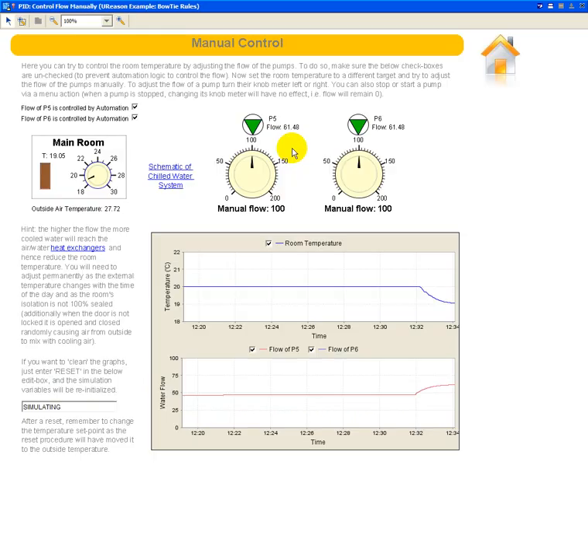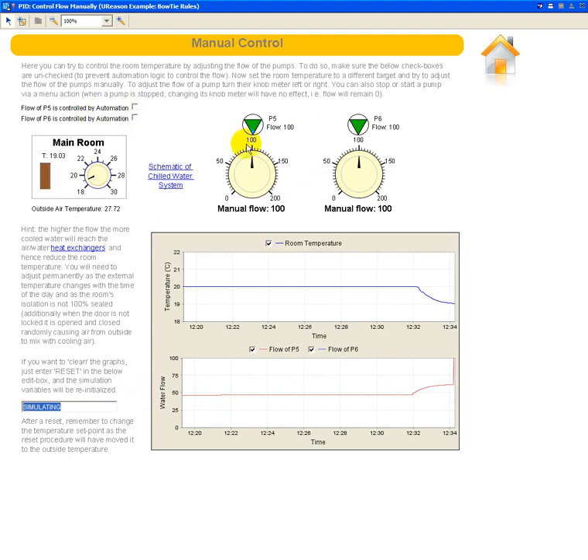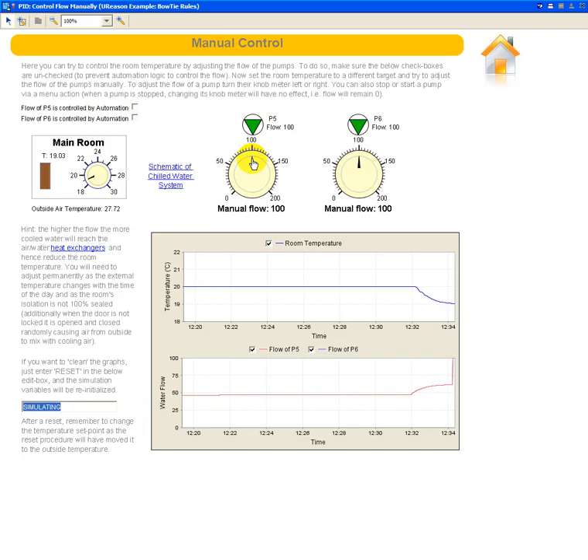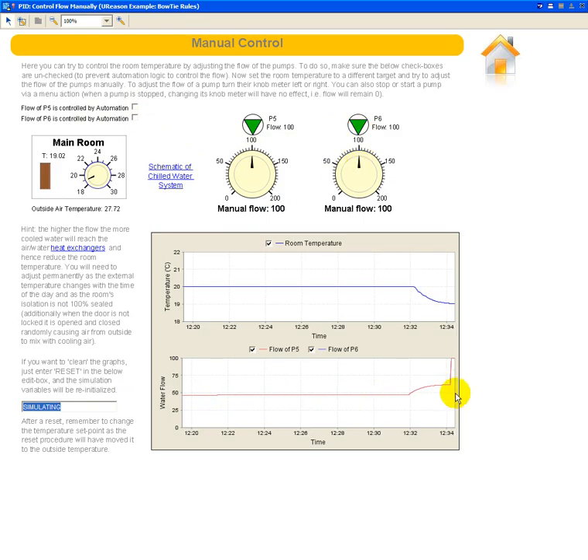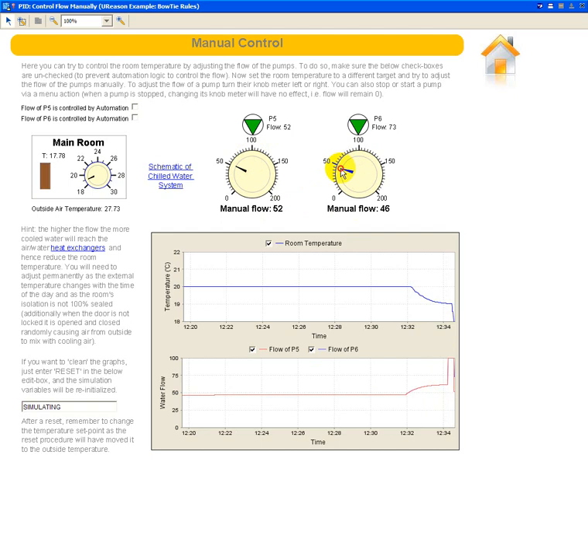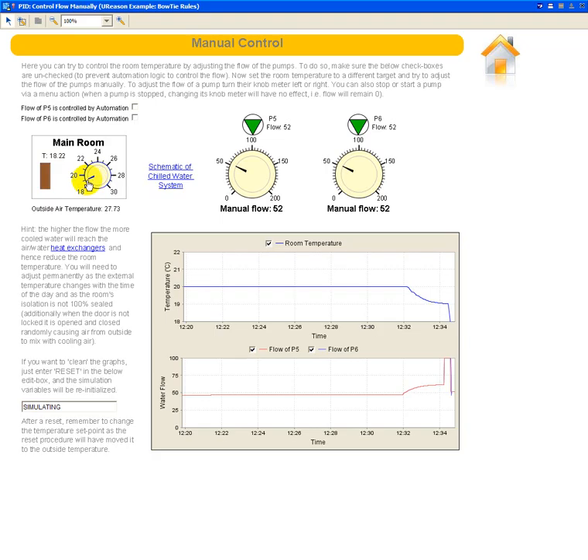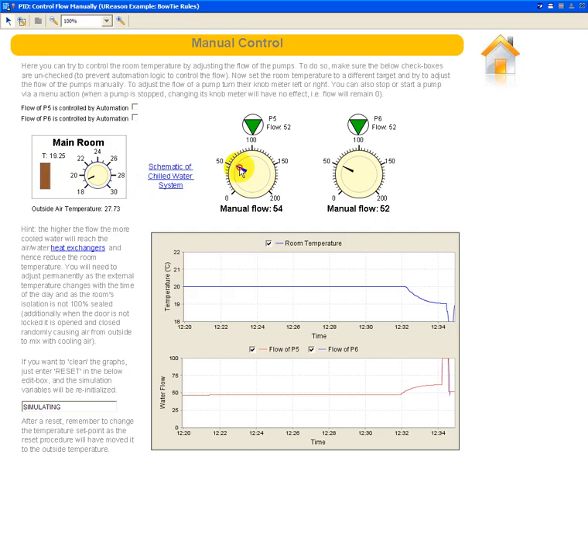So that is to show you how the automated version of the simulation can be done. We can also try to do this manually. And to do this manually, I have this page here where I can just disarm the control of the flows by the PID and manually control. So now these pumps are running at 100 instead of running around 50 or 60, so they will obviously cool down the temperature of the room. So we probably want to reduce the flow of these pumps to something around 50 again and see if that affects the temperature, if we can get back the temperature around the 19 degrees, because that is the value that we wanted here.